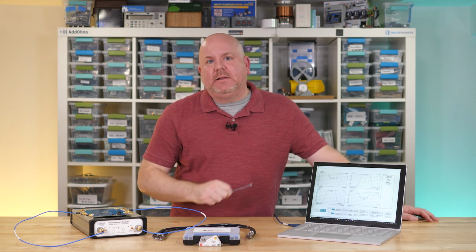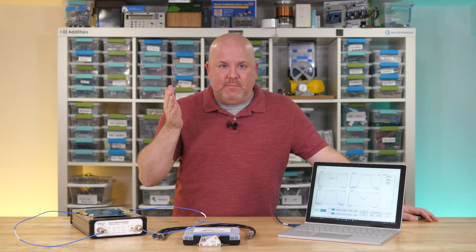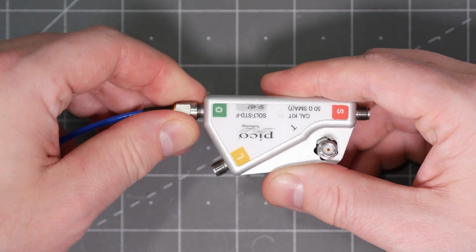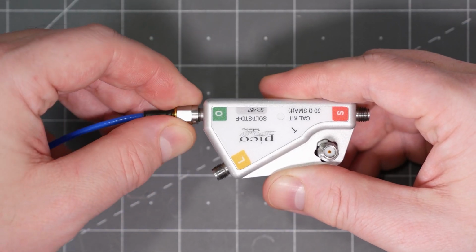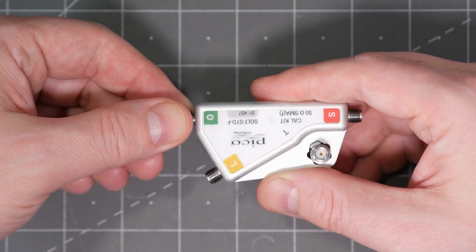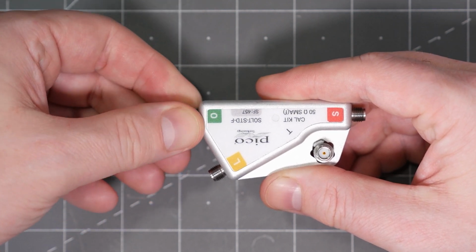The main reason I bring this up is that you should never mate an SMA to a proper 3.5mm, because you'll damage the 3.5mm. Speaking of damage, for any RF connector, always twist the side with the nut. You must resist the temptation to twist the other side. Doing so can and will damage that conductor.